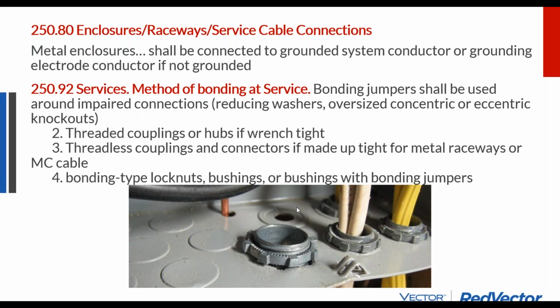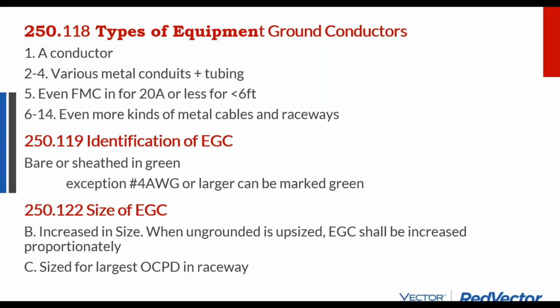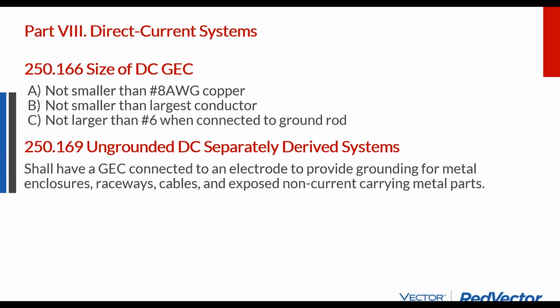So sometimes you'll see these knockouts and these lock rings with a grounded wire attached or one that's not attached. And it depends not even just on whether you're using a metal box, but what knockout position you're using within that metal box. Your equipment grounding conductor has to be marked green, unless it's number 4 or larger, in which case it could be taped green. So we start to see the electric code requirements begin to repeat themselves as we go through. If you're coming into the next month's webinar, we're going to start with the battery and solar section. So what we really didn't get to today is the Article 300 wiring section.